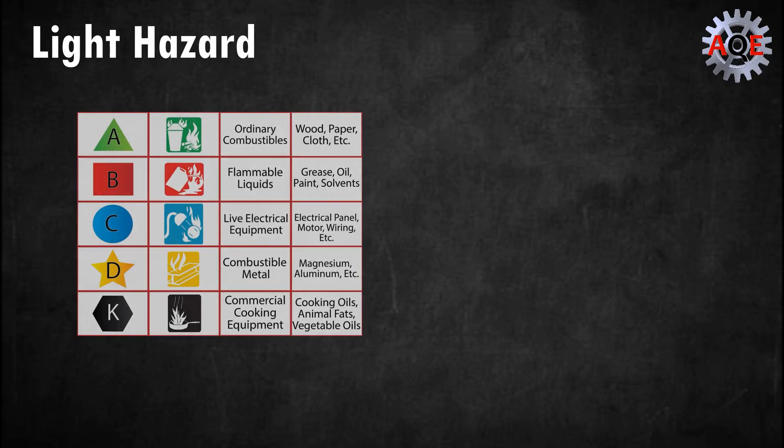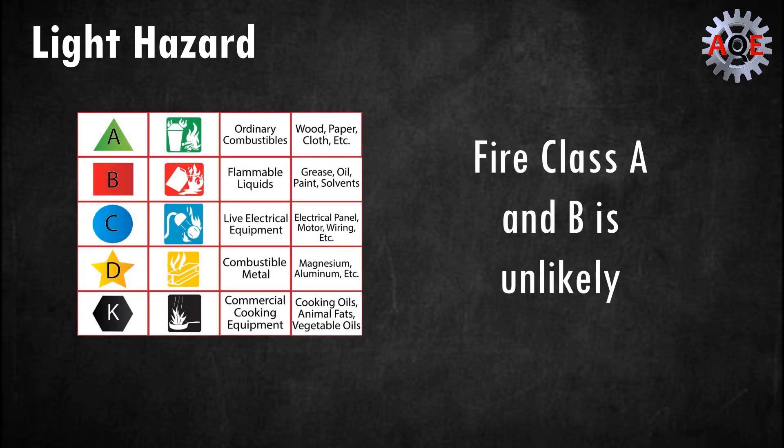Light hazard. These are locations where combustible products and the quantity of class A combustibles and class B flammables are incredibly unlikely. Class A combustibles include paper, refuse, and fabrics among others, while class B flammables include flammable liquids.